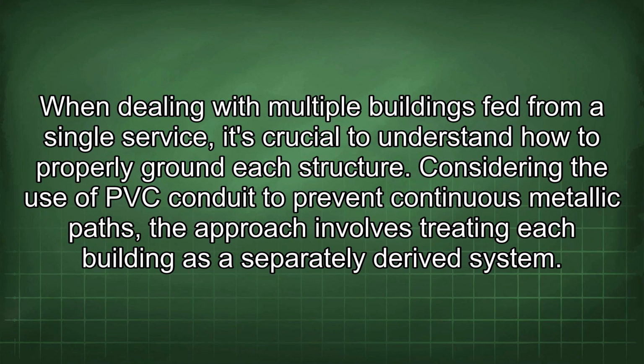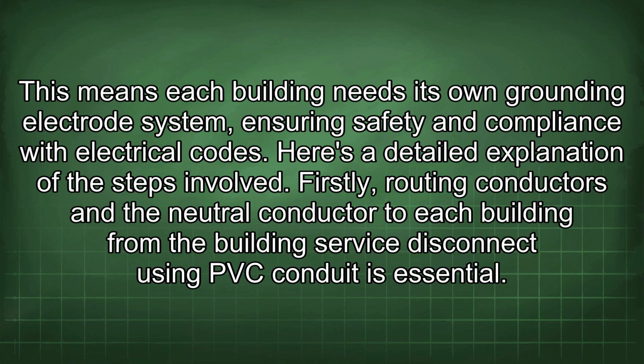When dealing with multiple buildings fed from a single service, it's crucial to understand how to properly ground each structure. Considering the use of PVC conduit to prevent continuous metallic paths, the approach involves treating each building as a separately derived system. This means each building needs its own grounding electrode system, ensuring safety and compliance with electrical codes. Here's a detailed explanation of the steps involved.